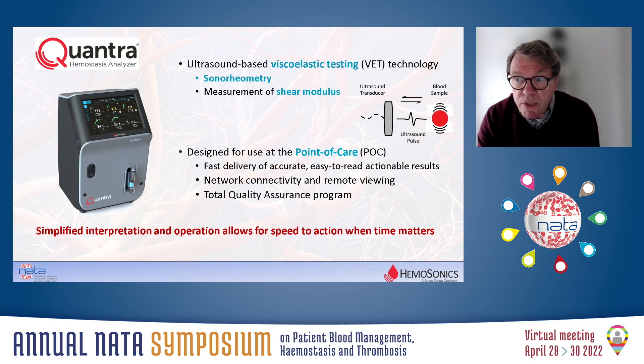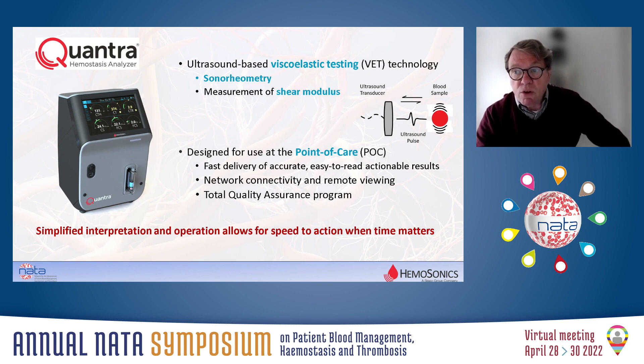The Quantra system is a small tabletop device which has really been designed for use at the point of care. Importantly, the system allows the direct measurement of the physical properties of the whole blood sample, referred to as the shear modulus, and is doing that by applying ultrasound technology, referred to as sonorheometry, which is a proprietary technology of the company.